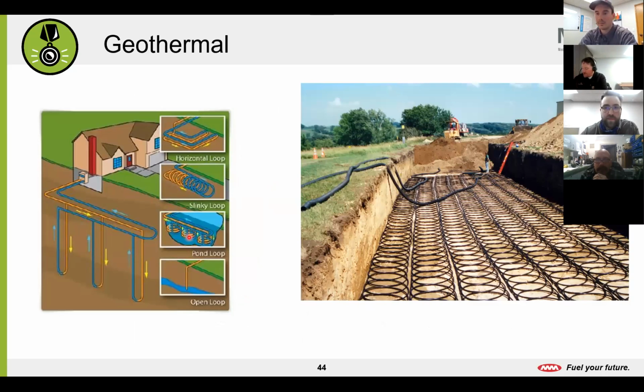Okay. It's interesting to note too that the biggest building in Seattle, Columbia Center, is all a hydronic heat pump loop. Oh yeah. It's not new technology, but done right, man, it can be very efficient. Yep, especially during the times where half the building wants heat, half the building wants cooling, and then later in the day, the other half wants heat, the other half wants cooling. We get a lot of that, so we're a really good climate for it, and it's everywhere.